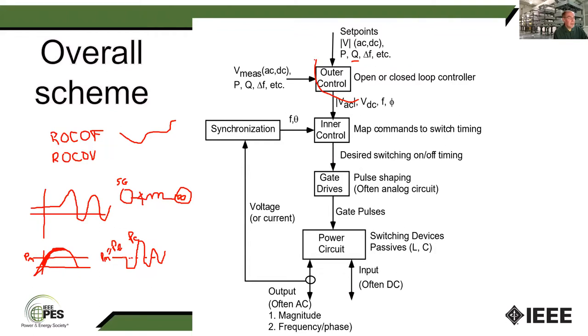So here, this is during the disturbance. If we're thinking of having energy storage, what matters is after the disturbance. The energy storage is supplying the extra power here to imitate the effect of the inertia of the machine. Here it's absorbing power to imitate the inertia of the machine. Here it's supplying power again, here it's absorbing power again. So you would need enough energy storage to imitate this. As a simple way of looking at it, you would put in a control loop that you program to imitate the standard swing equation that you see in the introduction to transient stability in a power system analysis book.